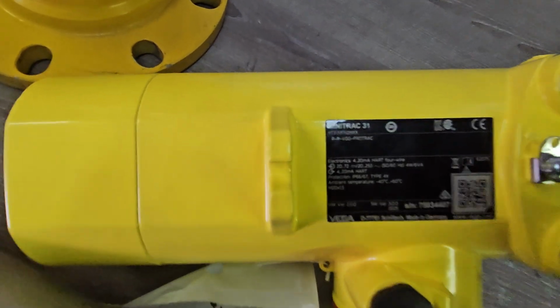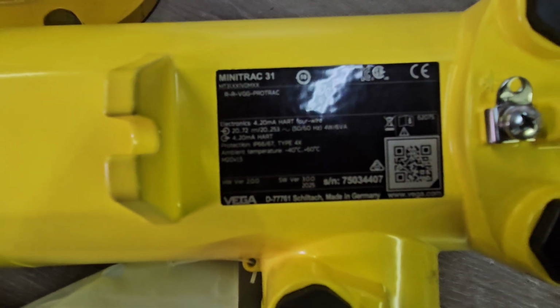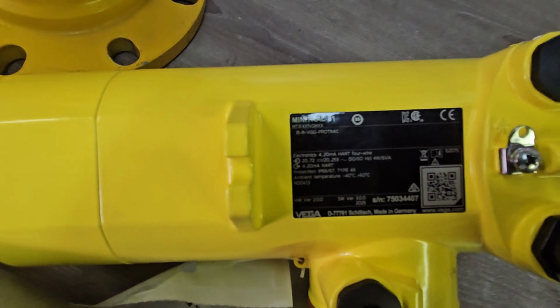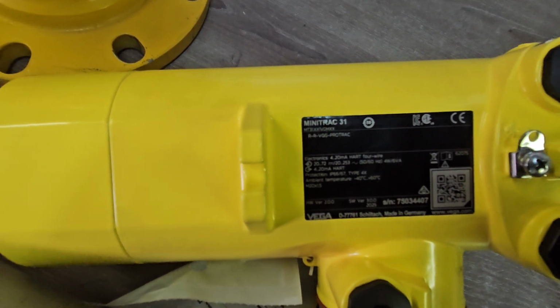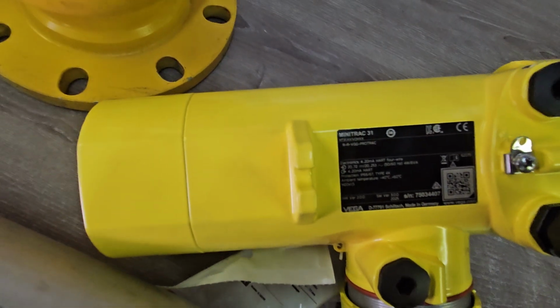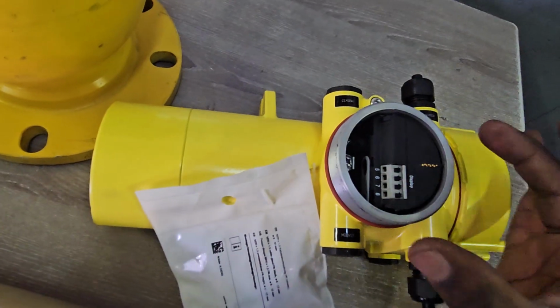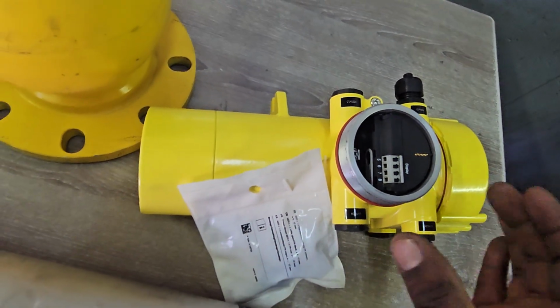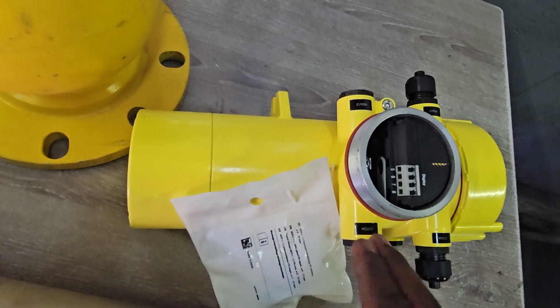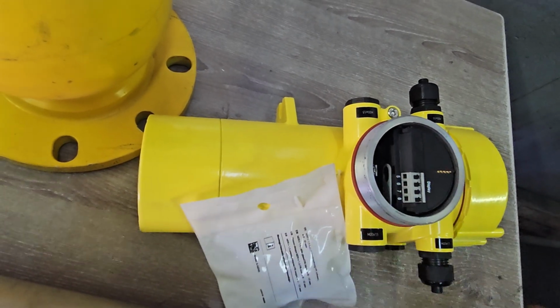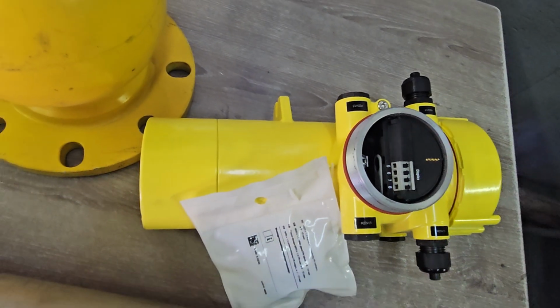So this is just telling you the power rating, how much power it needs to be powered, and the output that you're getting is a 4 to 20 milliamp. This side, you're probably going to have a display, something called a PLICSCOM. Install it there, and then you can set the parameters. You can actually connect the wiring as well there. And the other side is usually power. Okay.